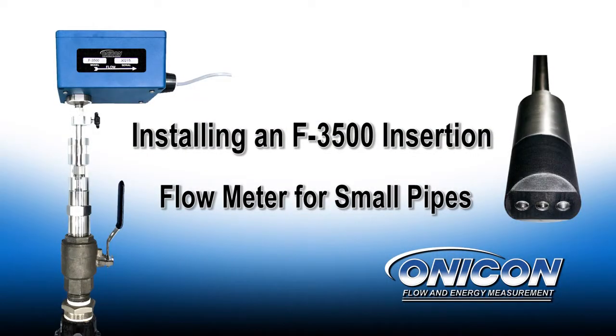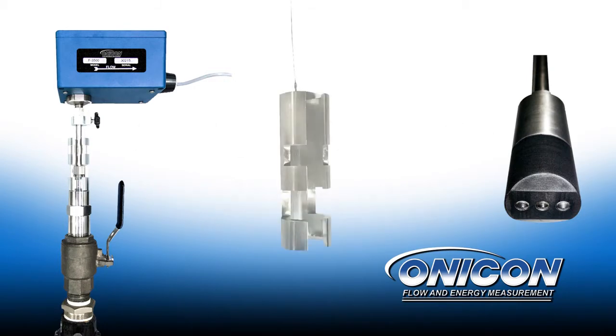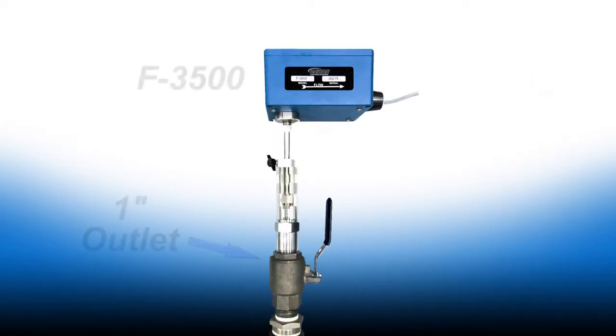Installing an F3500 insertion electromagnetic flow meter for small pipes using the provided insertion depth and alignment tool. This video assumes that the F3500 has already been threaded into the one-inch outlet on the pipe.